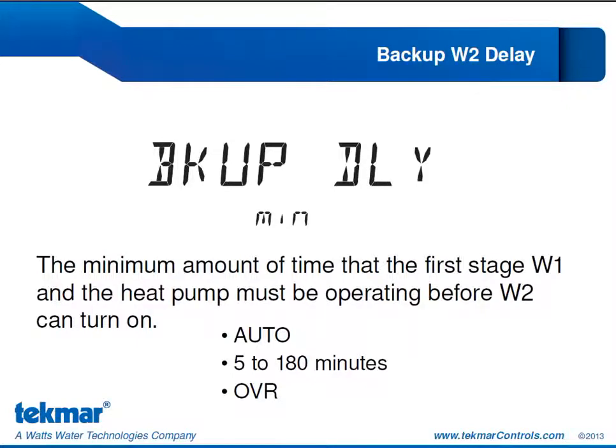The backup delay, or the W2 delay, is the minimum amount of time that the first stage, W1, and the heat pump must be operating before W2 can turn on. Now, two conditions have to be met for W2 to turn on. Firstly, we have to have that W2 differential met, and secondly, the W2 delay time must have expired. We can configure this for auto mode, in which there is no additional delay, or for a time ranging between 5 to 180 minutes, so we can hold off that W2 for up to 3 hours if we want to. Or we can put it into override mode, in which W2 will only turn on when we're in emergency mode. So in that case, our W2 really would be a backup source of heat.